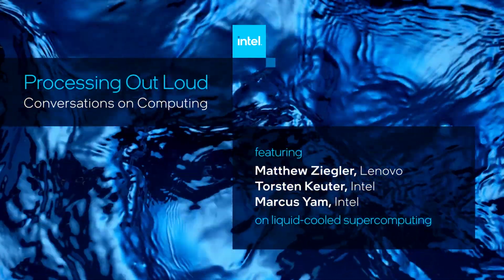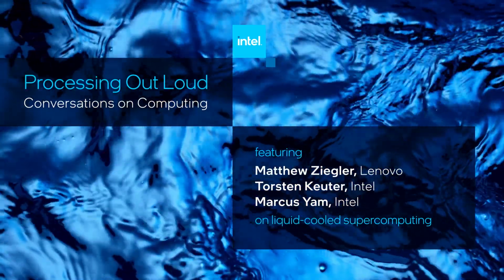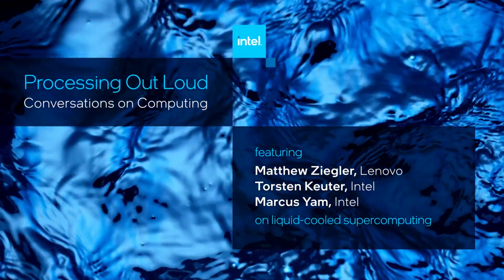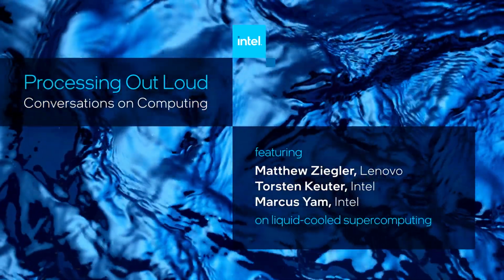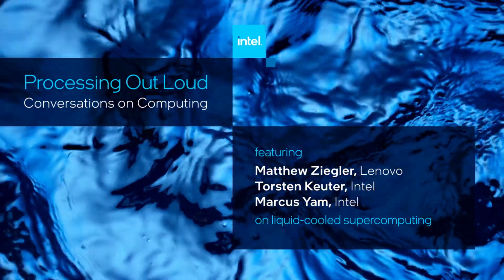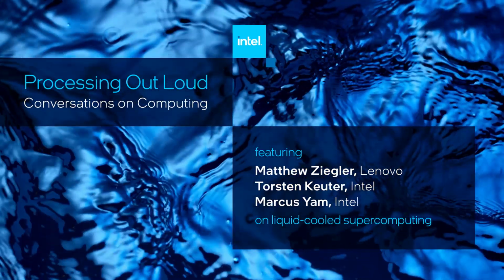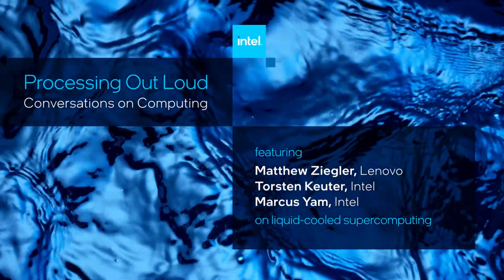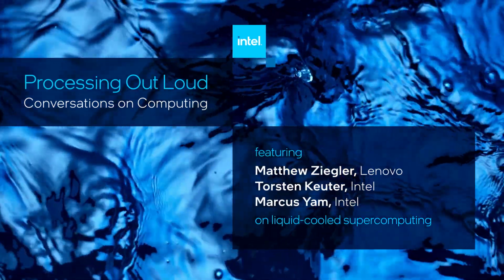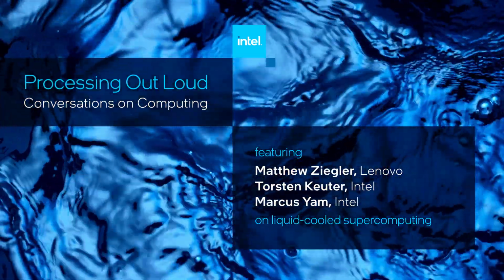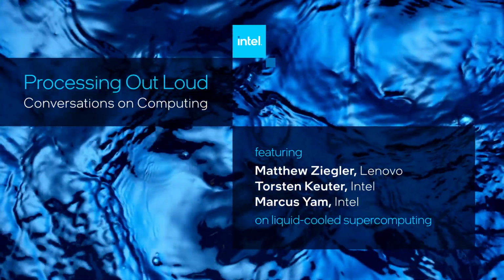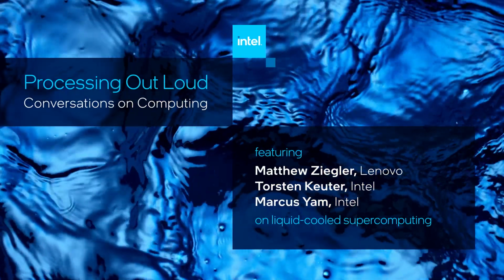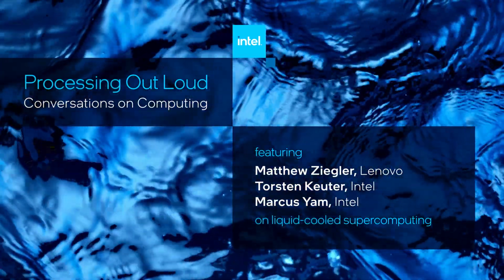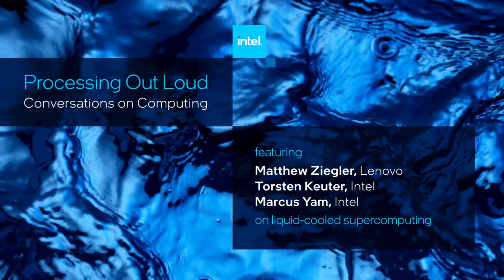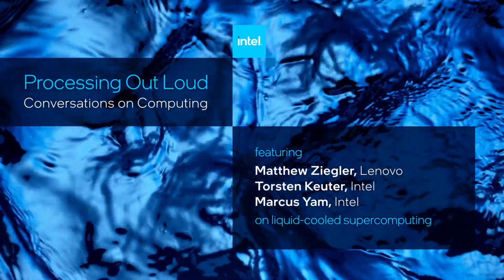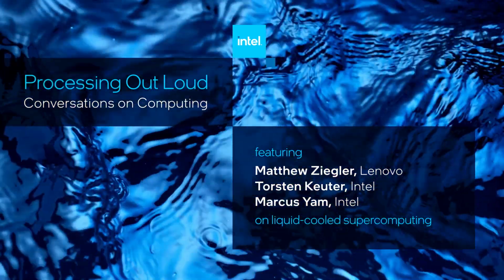A lot of this control is based on the thermal capabilities of the processor. Each processor has a limit, and if it gets too hot, it has protection mechanisms built in. The first thing it does is throttle frequency. So your processor might be rated at 2.3 gigahertz per core, but you look at it and it's running at 1.8. The lower the frequency, the less heat generated. So in air cooling, you often see these throttling events if your system gets too hot and your fans can't blow enough air over it. The processor takes safety into its own hands and says, I'm getting too hot, I'm going to shut down here.